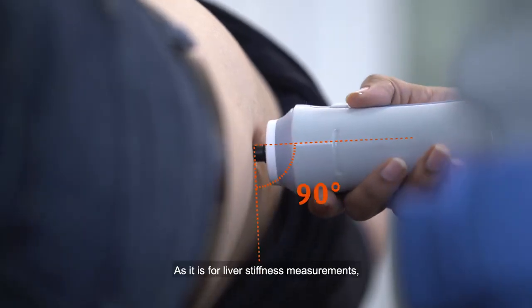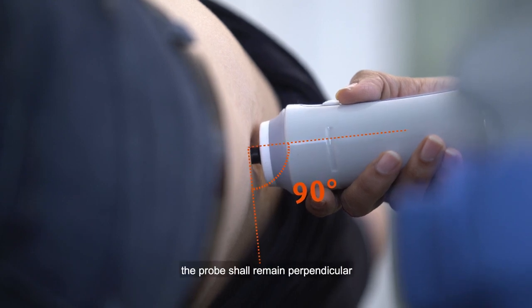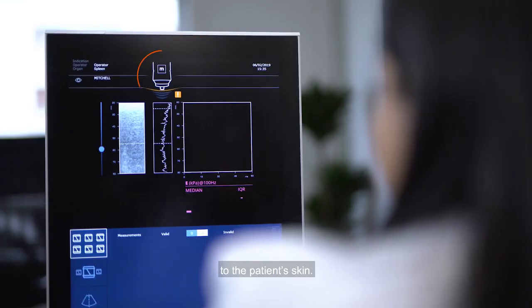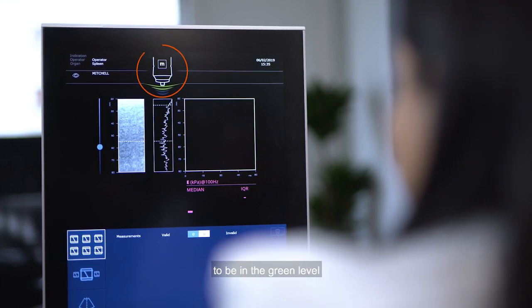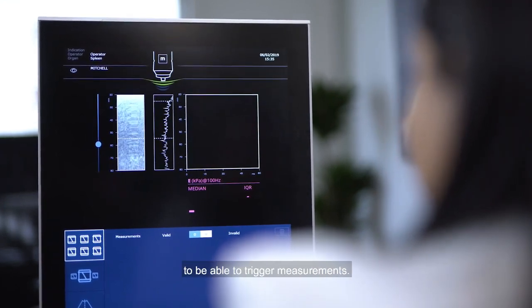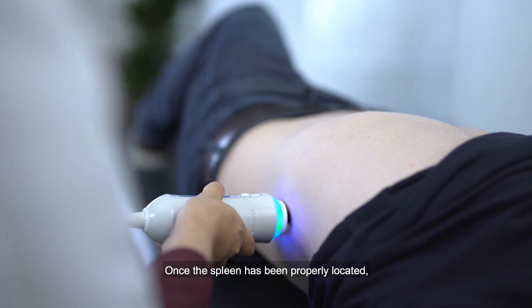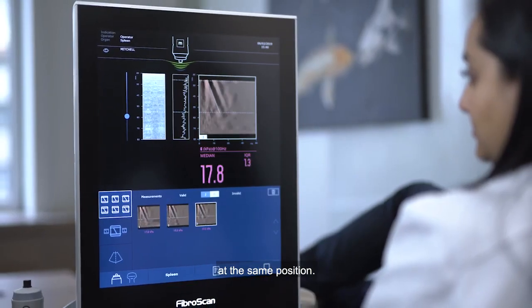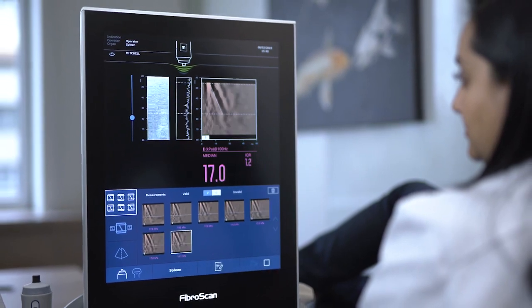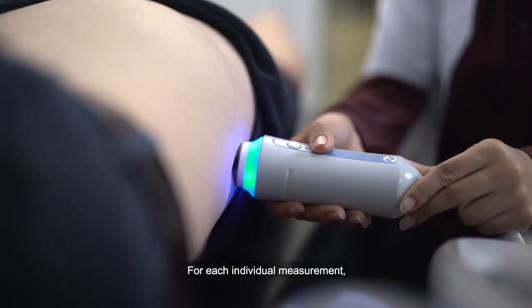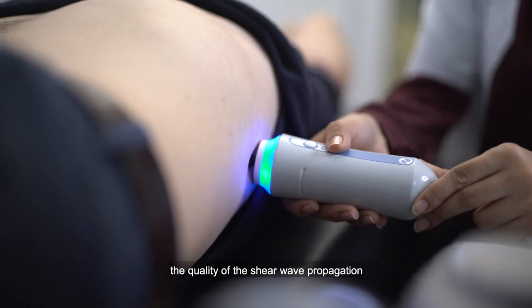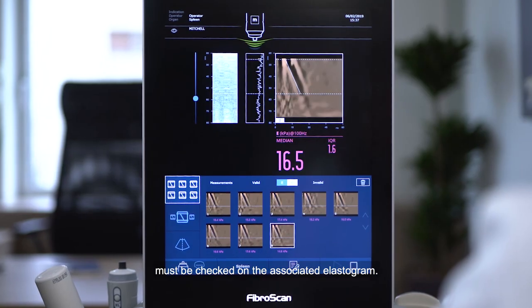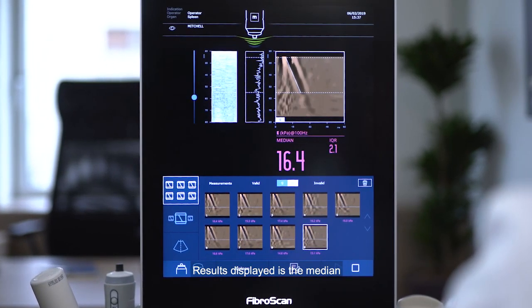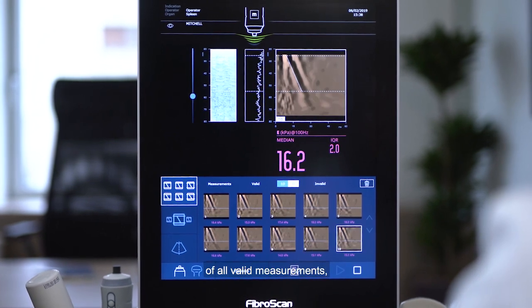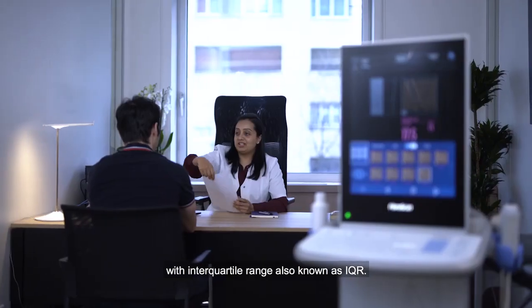As for liver stiffness measurements, the probe shall remain perpendicular to the patient's skin. The force indicator also needs to be in the green level to be able to trigger measurements. Once the spleen has been properly located, the operator shall trigger at least 10 valid measurements at the same position. For each individual measurement, the quality of the shear wave propagation must be checked on the associated elastogram. The result displayed is the median of all valid measurements, together with the IQR.